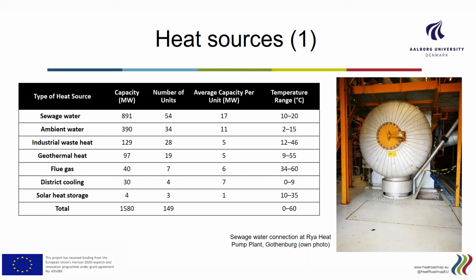Now, sewage water, as you can see, has the largest capacities. There are 54 examples found in Norway, Sweden, Finland, and Switzerland. And it has been in use since the year 1981. Approximately 56% of the installed capacity in Europe, out of the 1,600 megawatts thermal, is heat pumps using this type of heat source, sewage water, and it has a temperature range between 10 and 20 degrees Celsius. Also worth mentioning is that the sewage water used by the heat pumps is generally treated before use as a heat source, except for some examples in Norway.